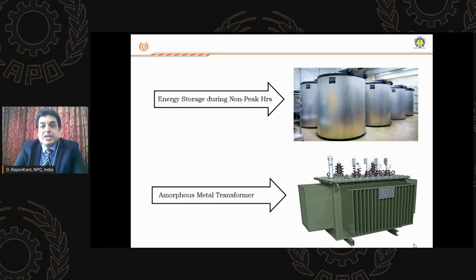Further, if you have a cold storage system, and nowadays a chilled water system, and you have a continuous cooling load even in the peak hours, you try to have the ice banks made in non-peak hours. You can switch off the compressor during peak hours and use this stored ice for cooling your system in the peak hour duration, which reduces a considerably great amount of energy.